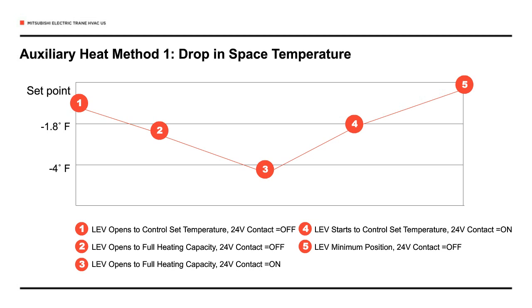And at that point, auxiliary heat is going to kick in at some predetermined temperature. We want to give the VRF heat a chance to heat the space, so you don't want to engage auxiliary heat too quickly. So we want a little bit of a deadband there of about 2 degrees. But then we can set that auxiliary heat to kick in anywhere between 2 degrees and 9 degrees Fahrenheit below space temperature. So if you have a set point of 72 degrees, you might kick the auxiliary heat on 3 degrees below that, say it's 69 degrees. Or you could let it drop a lot further and go all the way down to 63 degrees.